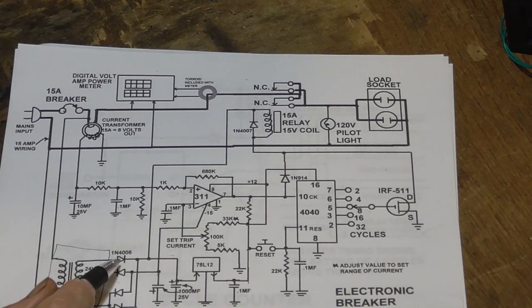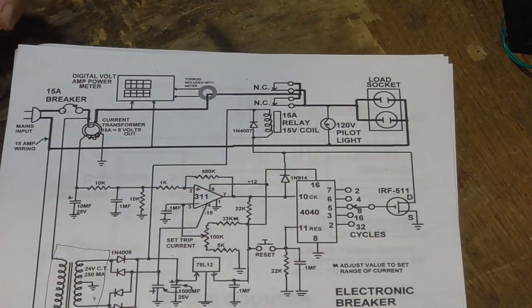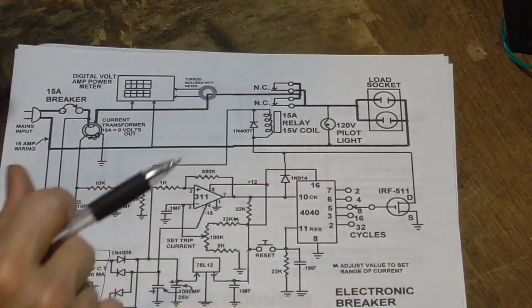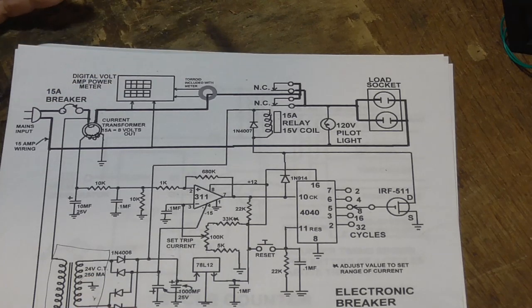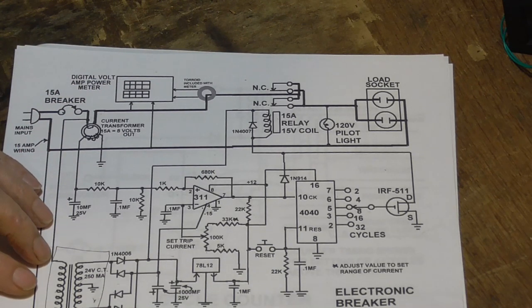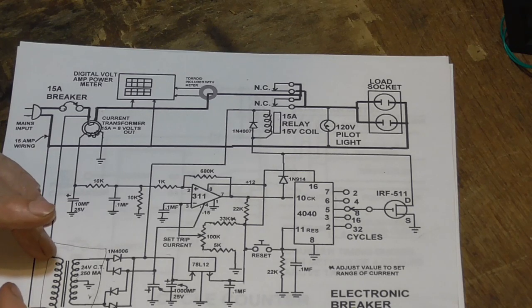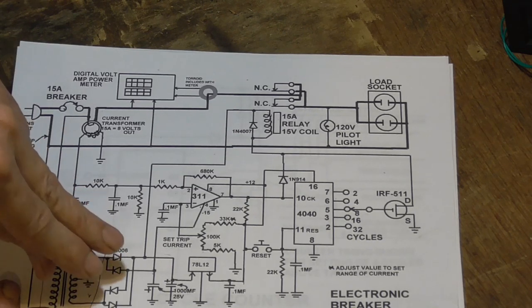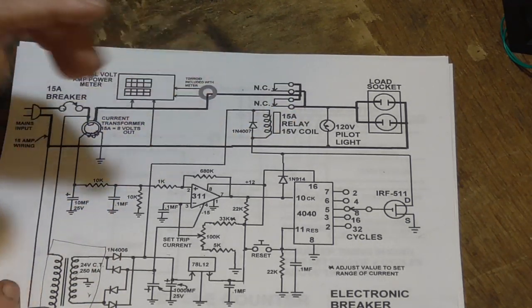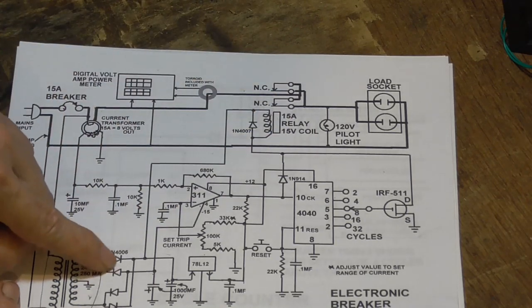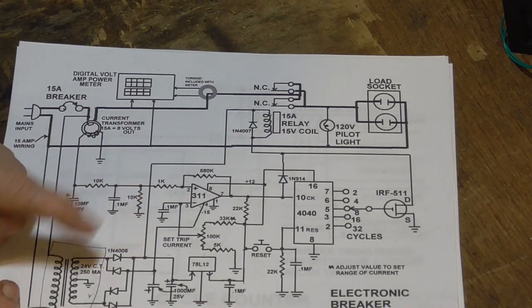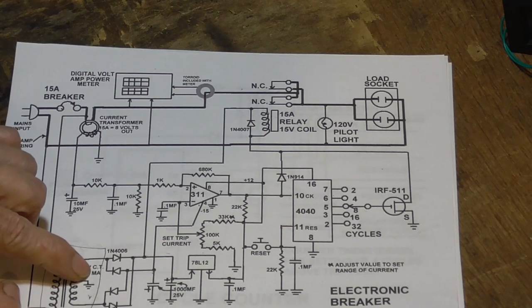Normally you'll go ahead and shut the power off if you blow it. If the thing pulls in and triggers, then you're going to want to shut the power off and find out what's wrong. Otherwise, you just push the reset button and the relay opens anyway, and you don't have any power in it. So it really just has to do with the relationship between your raw voltage here and the relay that you have, to make sure your relay coil can handle whatever the raw voltage is out of your power supply.